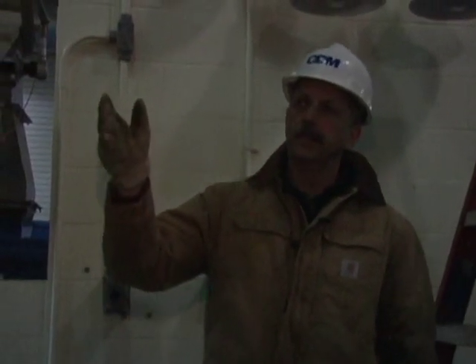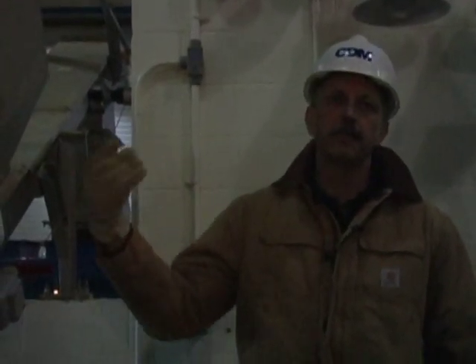When the conveyor is brought online, there's a couple things. There's a spray mechanism that is a solenoid valve on the spray line that discharges water onto the trough below the belt in order to clean the trough off, keep the material from caking up.